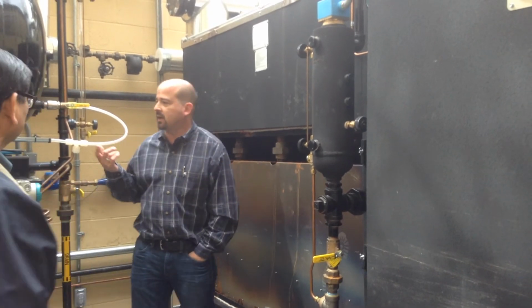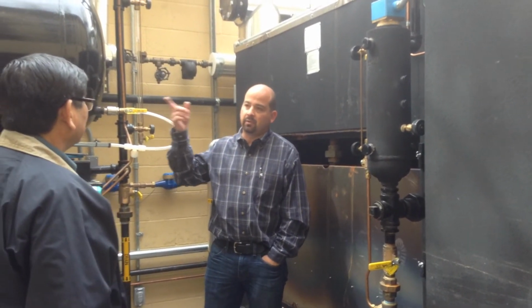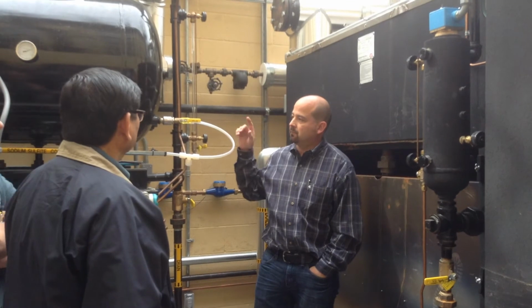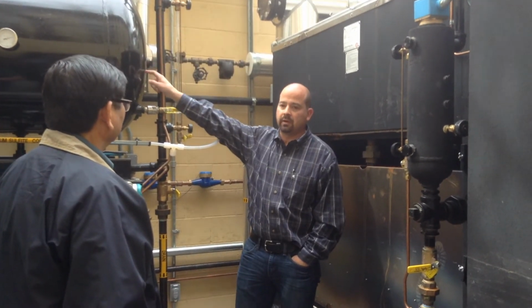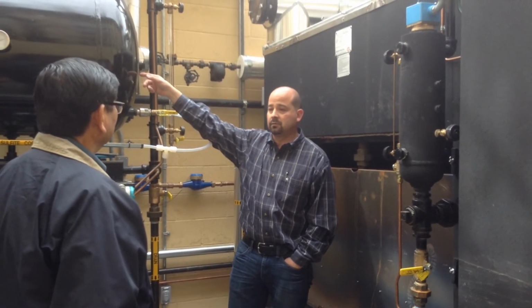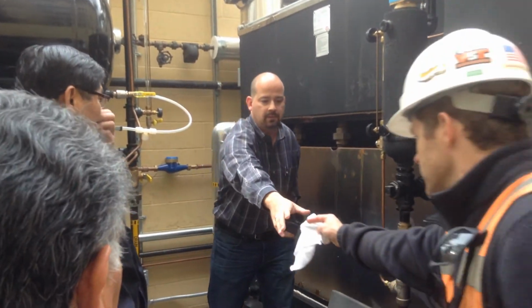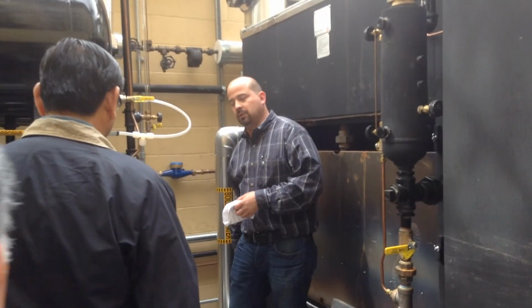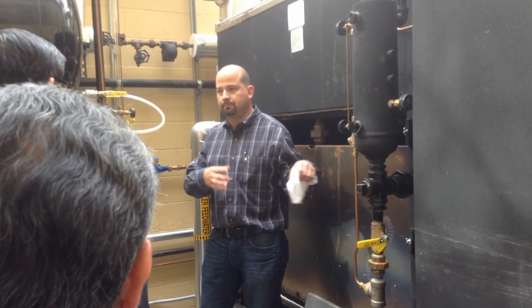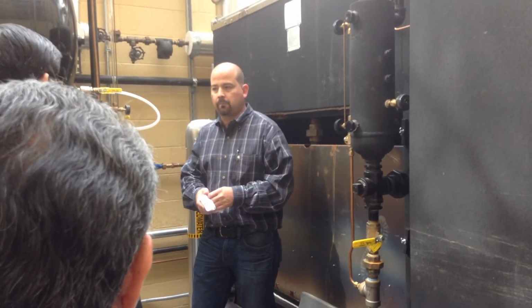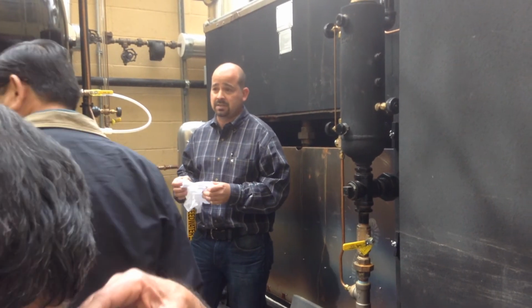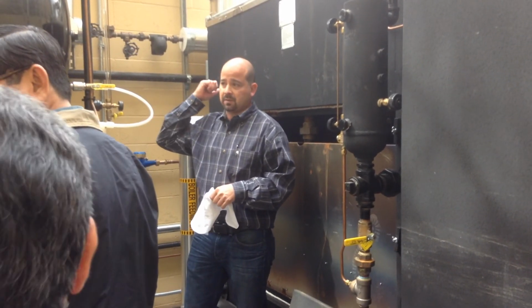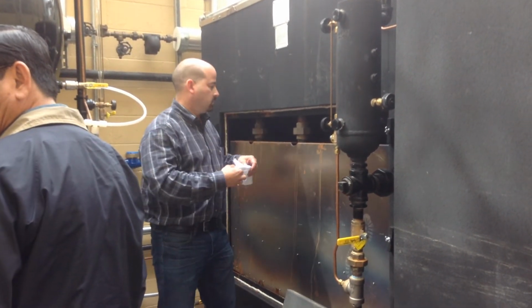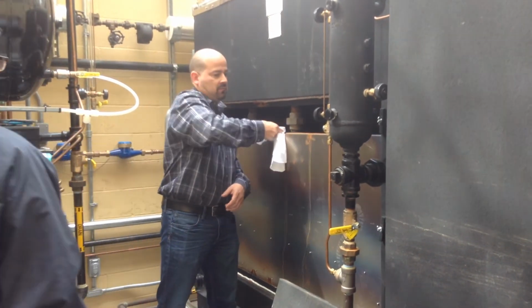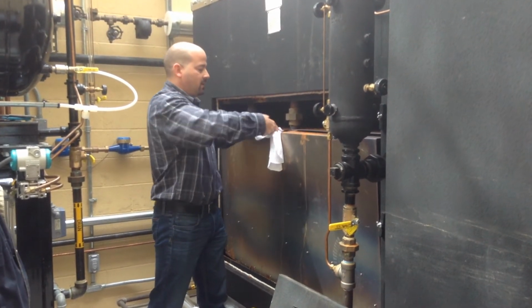While they're getting a rag, the chemicals, probably similar to the rest of your campus, you have sulfites that go into the deaerator, and that's to reduce oxygen, an oxygen scavenger. You have phosphates. Phosphates is a scale cutter. That's what reduces the scale buildup in the boiler. Then you have amines, which goes into the steam system to treat the steam line. It's fun getting back on.